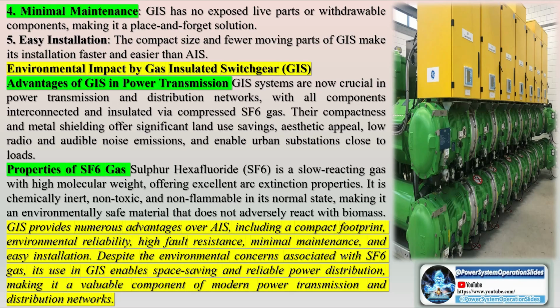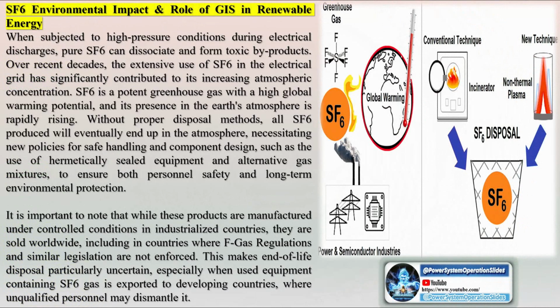Hybrid switchgear combines gas-insulated switchgear with solid insulated screened busbars, addressing many of the issues faced by utilities with traditional GIS. This hybrid approach eliminates the need for SF6 in the busbar compartment. Given the high global warming potential of SF6, reducing its use is crucial. The introduction of plug-in type voltage transformers and outer cone cable bushings, which can also accommodate current transformers, offers better accessibility and reduces the size of SF6 filled tanks restricted to switching units only. This leads to a 30 to 50% reduction in SF6 consumption.